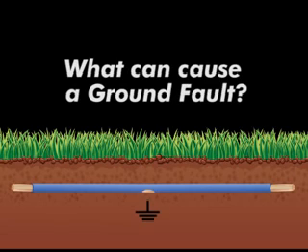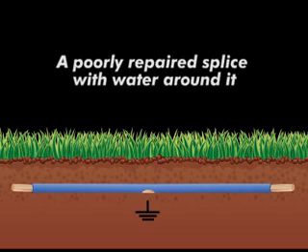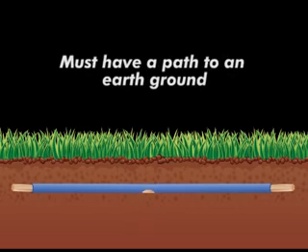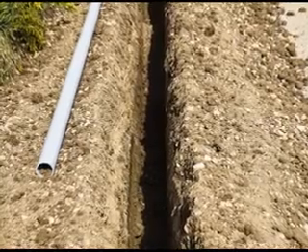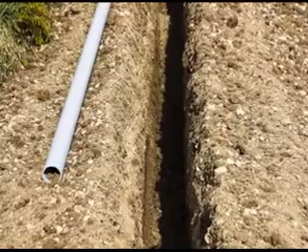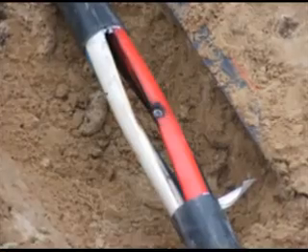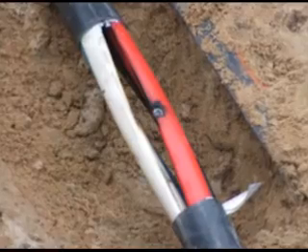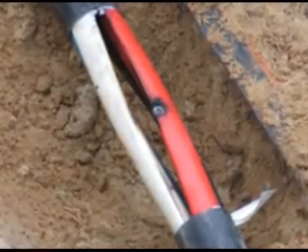What can cause a ground fault? A nick or cut in the insulation, or a poorly repaired splice with water around it. A current must have a path to an earth ground to be a detectable ground fault. In most cases, a cable contained in a conduit will not have a detectable fault to ground. One exception would be a PVC non-conductive conduit that is completely severed, exposing the conductors to the earth ground.